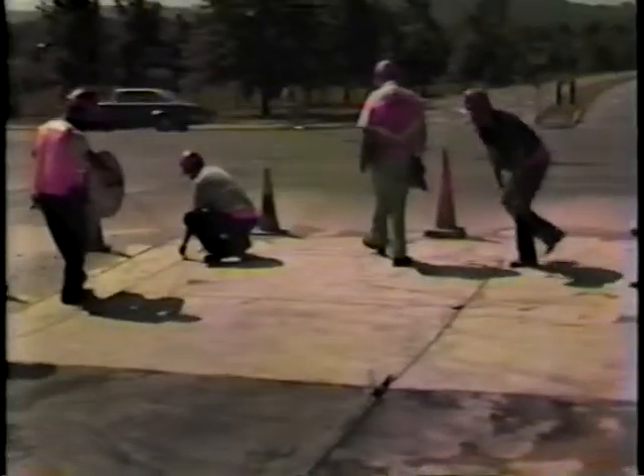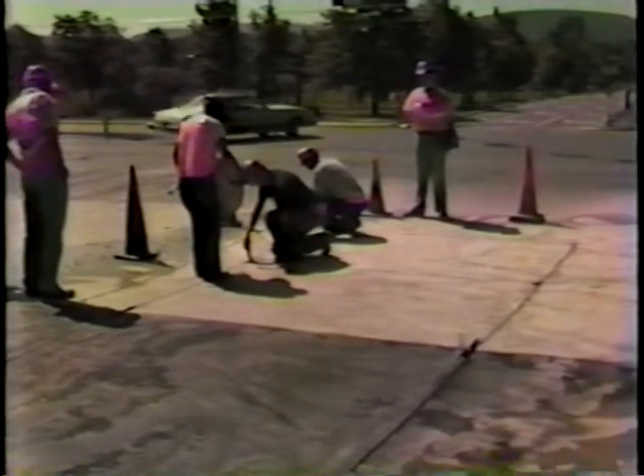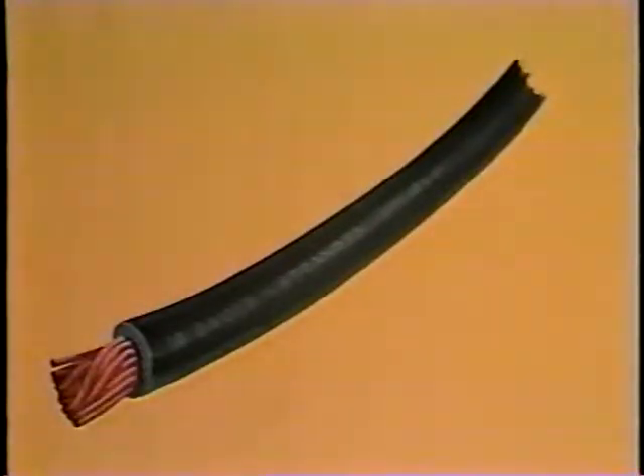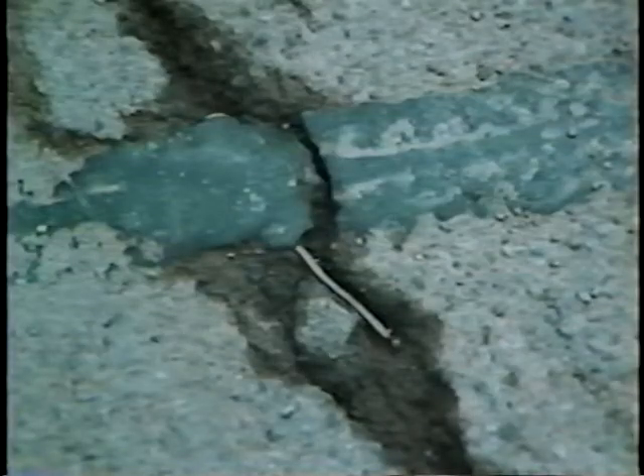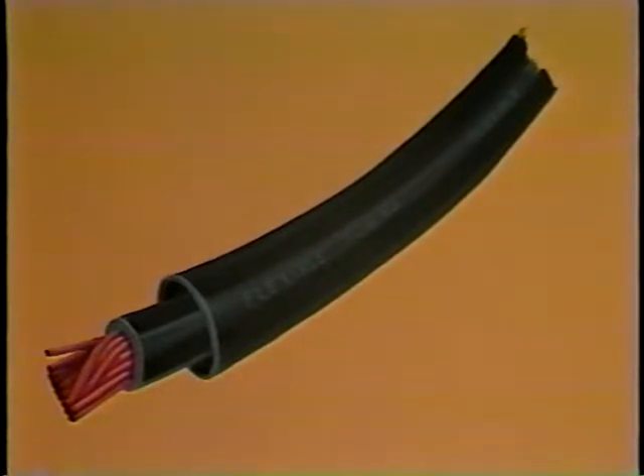Based on the failure survey, a large percentage of failures could be prevented by using a more durable wire. Most failed loop systems studied were constructed according to a specification calling for 14-gauge stranded copper signal cable with a polyethylene insulation. This wire could not survive the stresses caused by even minor pavement disruptions, such as creeping, cracking, and thermal expansion and contraction, nor could it withstand exposure to water and debris from minor sealant failure. It was found that the use of 14-gauge stranded copper wire loosely encased in a flexible vinyl tube had been very successful in other states' loop detector installations.